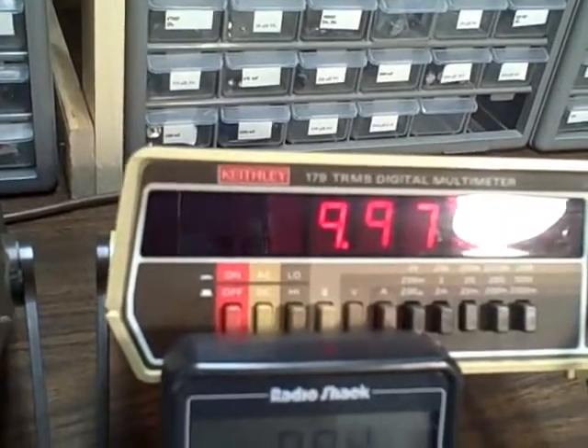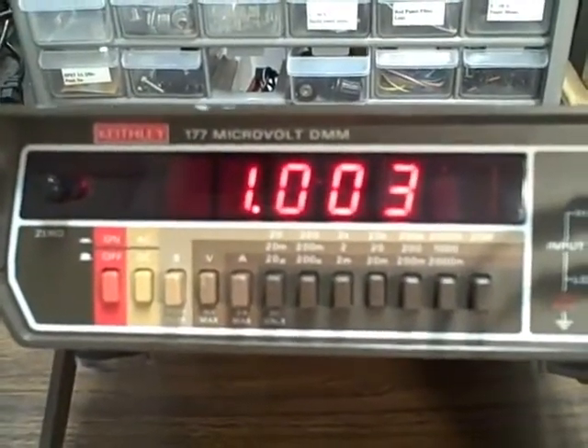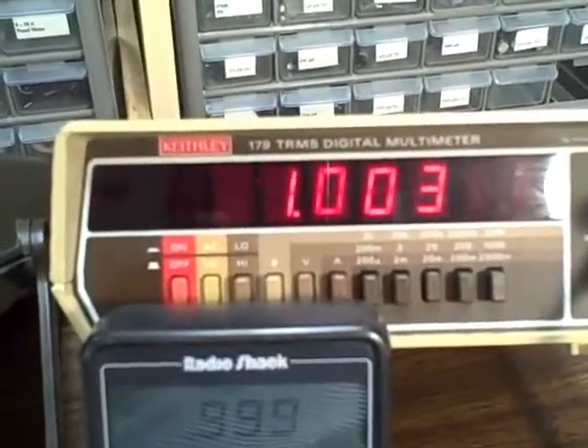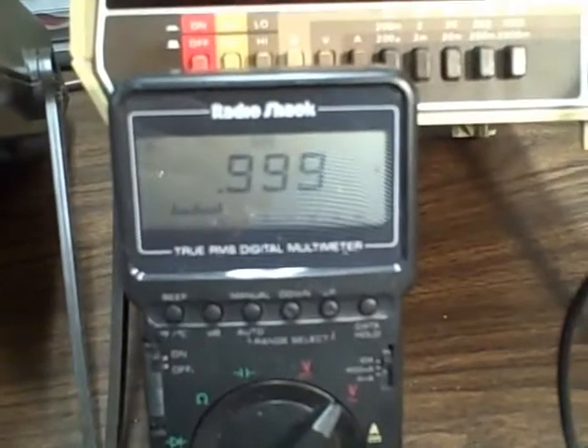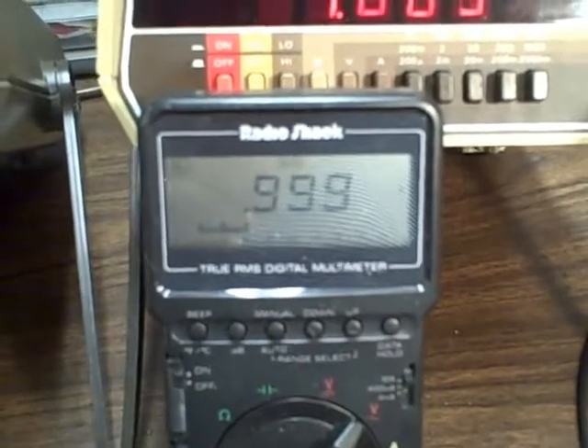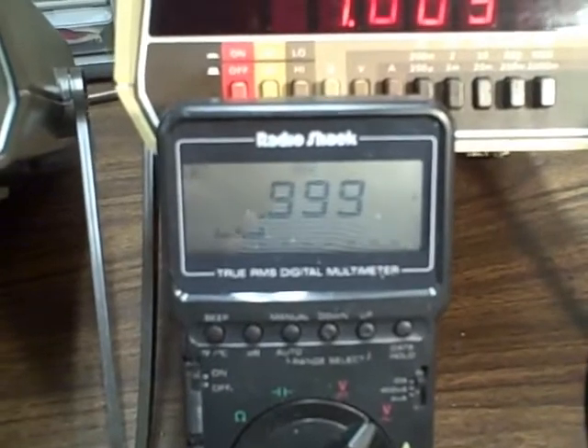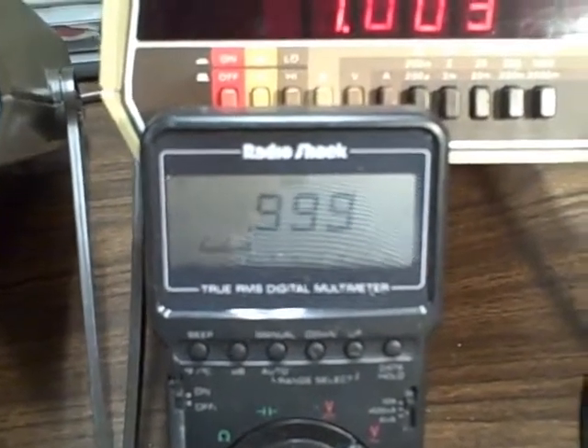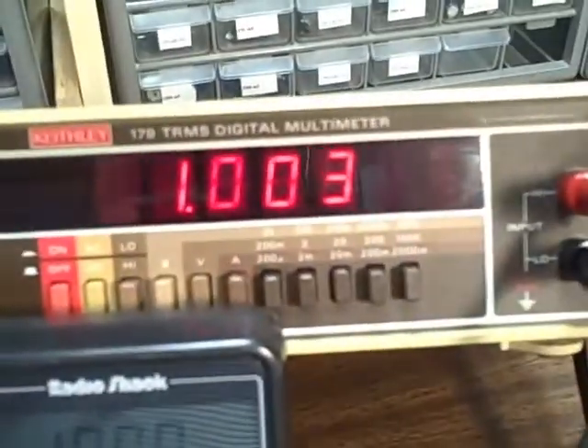All right, we're going to go ahead and change the voltage. We'll bring her down to roughly a volt. We are at the moment reading 1.003 on the 177, 1.003 or 4 on the 179, and 0.999 or 1 on the Radio Shack. So we're within 3 to 4 millivolts on all three units, and the 177 and the 179 are in very, very close agreement to within a millivolt. This is at 100 hertz.